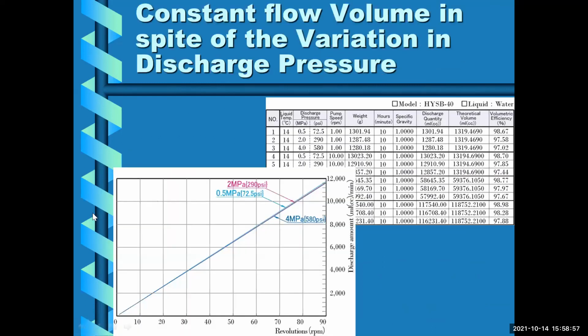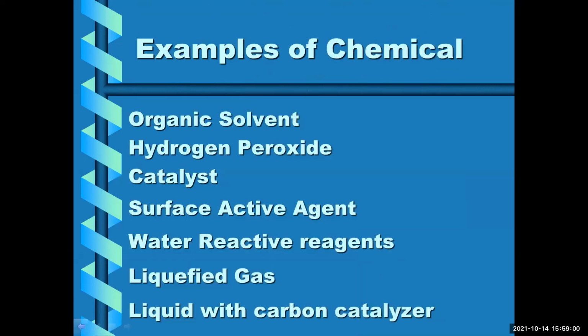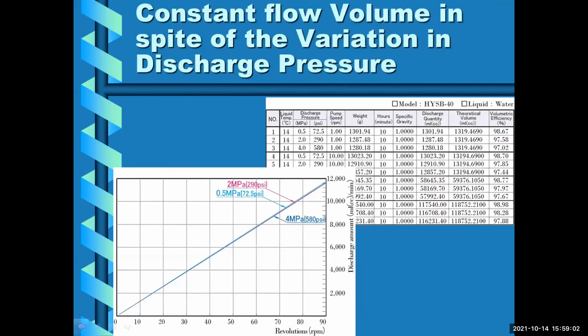The slide shows constant flow volumes in spite of variation in the discharge pressure. This is a very important feature for continuous flow applications with microreactors because the pressure inside the microreactor fluctuates. So you see virtually the same flow rate lines at various discharge pressures.